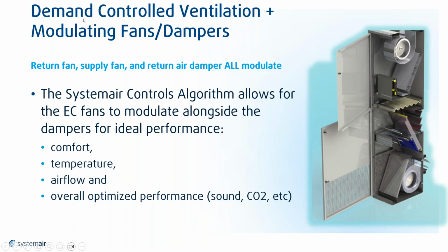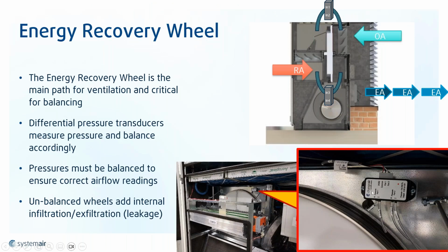So all these units are demand control ventilation. They're decentralized ventilation where the fans are electronically commutated and they modulate with the dampers. So you get the best of comfort, temperature, airflow, optimized for sound and CO2 levels in the classroom. Each of the dampers has its own actuator, whether they are modulating. So for example, if you have 500 parts per million, we crack open a bit of that outside air. If you have the energy recovery wheel, it goes through it just a bit. And then if we have 1,000 ppm of CO2, then we bring in that 450 CFM of air through the wheel, for example. The energy recovery wheel works with dual pressure transducers. We have 2 pressure transducers measuring the pressure across the wheel. So it's to control a supply fan, an exhaust fan, and an outside air damper modulator. So it works on a perfect algorithm.